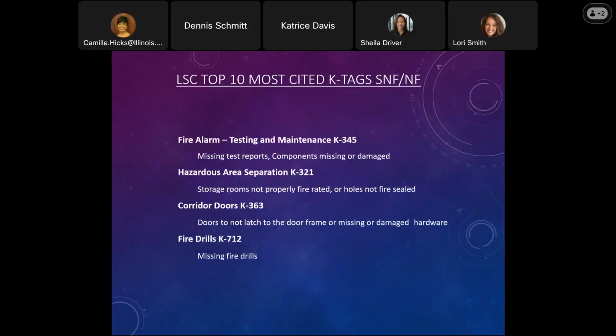Fire alarm testing and maintenance is probably number 2 overall for all facilities. We're missing reports, components are missing or damaged in the fire alarms. The number 1 item we always run into is sprinkler testing, documentation missing. They haven't checked certain older devices that need to be updated, changed, or checked. So sprinkler and fire alarm are probably number 1 and number 2 for all facility types.